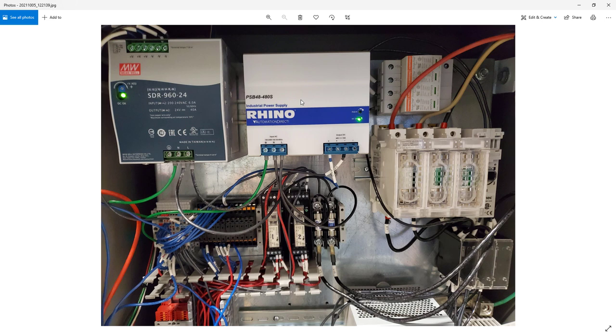So there were two things that could be done. One was a 5 to 1 gear reducer and the other is to go from 24 volts up to 48 volts. And if you know electricity at all you know that 48 volts at the same current will give you twice the power. So and this was actually a recommendation by AMCI who manufactures these stepper motors. They're very nice. They have the controller, the driver, and the ethernet interface all built into one. And it has two ethernet connectors on it so you can daisy chain. So we had to add this 48 volt power supply for those stepper motors.